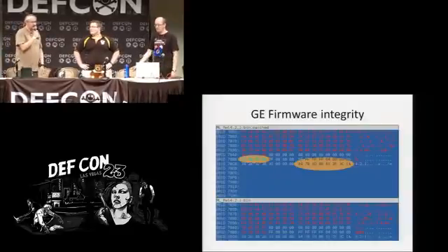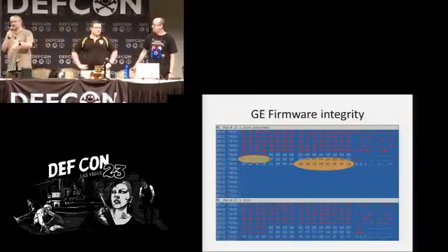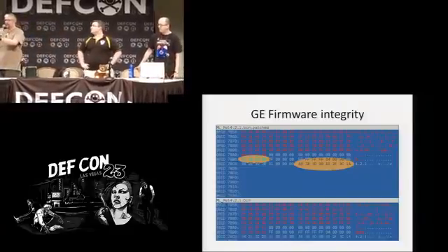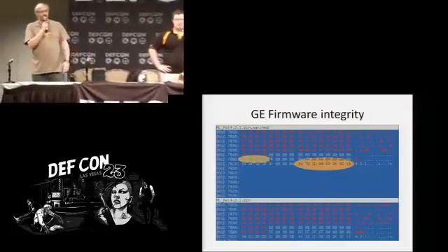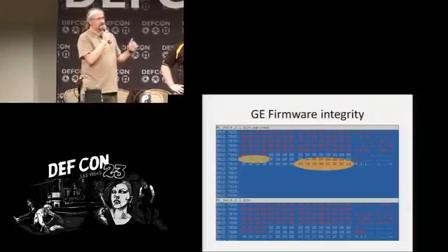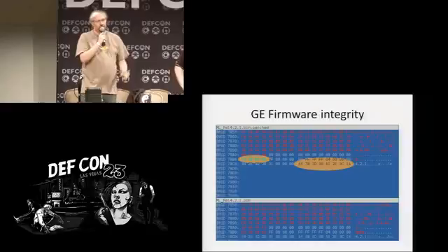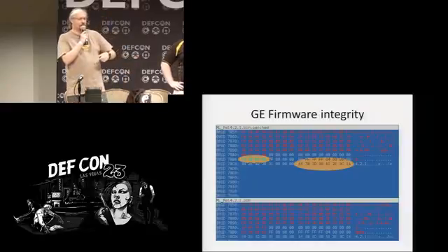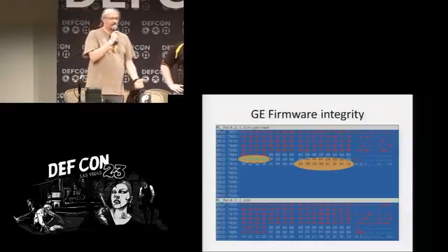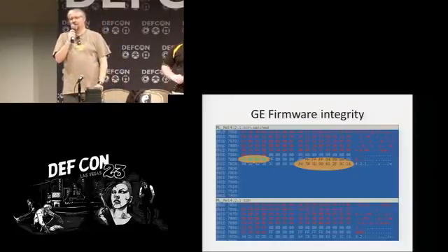So, GE firmware integrity. Remember earlier I didn't want to brute force that password that Ashish Campbell of Qualys brute forced. The reason I didn't want to do that is because I can patch in my own keys in firmware and then run a CRC Adler at the end, and then try and reverse the algorithm at the bottom. So there's basically two checksums. One's code signing more than checksum. And if you patch in your own key with your own password, it turns out that just works, and you don't have to do any brute forcing. So top tip there.